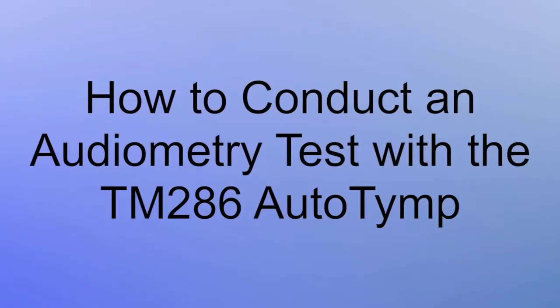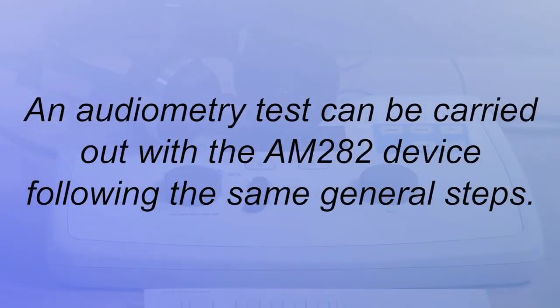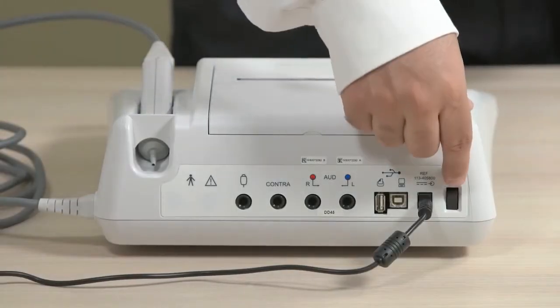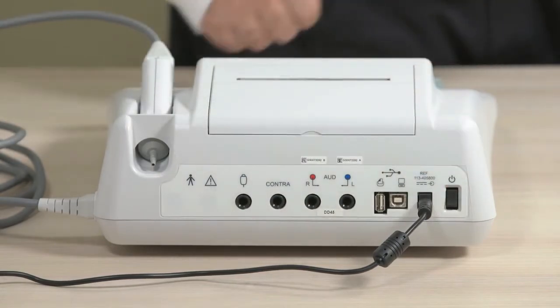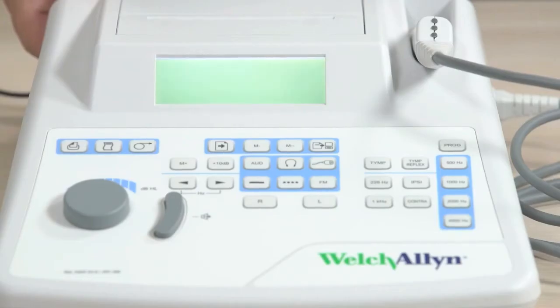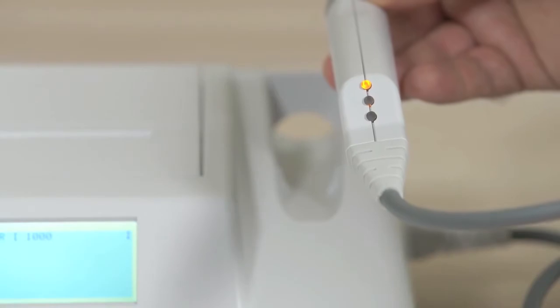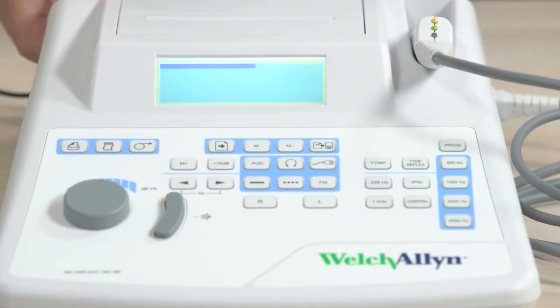Now we'll review how to conduct an audiometry test with the TM286 device. An audiometry test can be carried out with the AM282 device following the same general steps and using the same buttons and knobs. You'll turn on your device here. When power is turned on, the LCD will be illuminated and the orange light on the probe will be lit. The display on the LCD will show a scroll bar across the top to indicate the system is initializing. Allow the instrument 10 minutes to warm up.